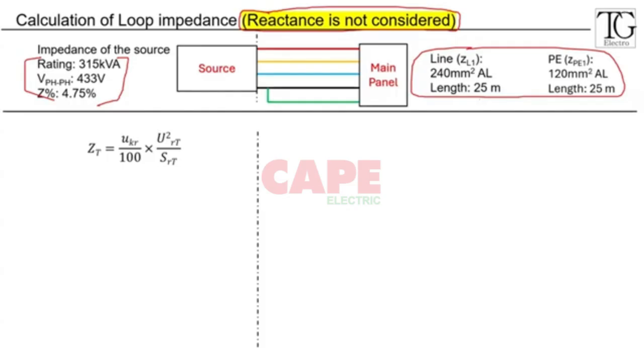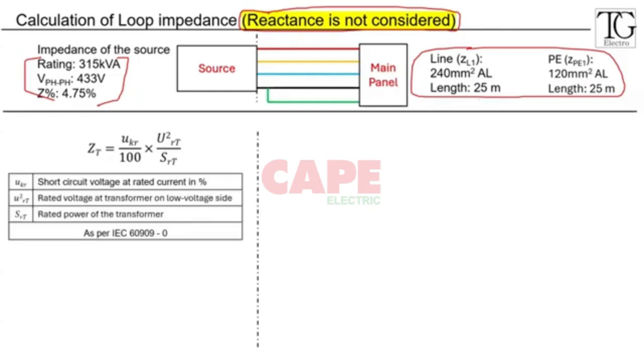Obviously, everybody in the design industry will know how to get the Z impedance value. So this is the value, and this is the formula for it: the short circuit Z percentage divided by 100, into the voltage squared by rated power. So this is the basic formula. It is also mentioned in IEC 60909 part 0.